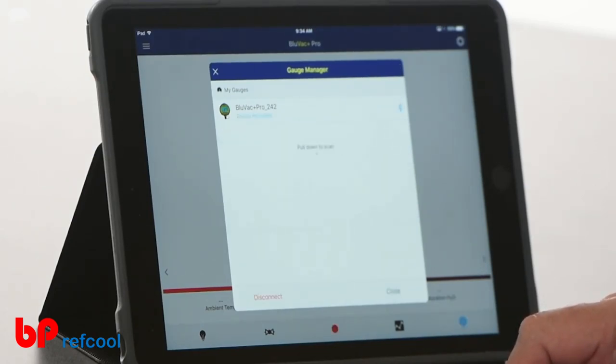It's going to show that the device is activated. In a second here, it's going to pull up about 760,000 microns, because we're at atmospheric pressure.